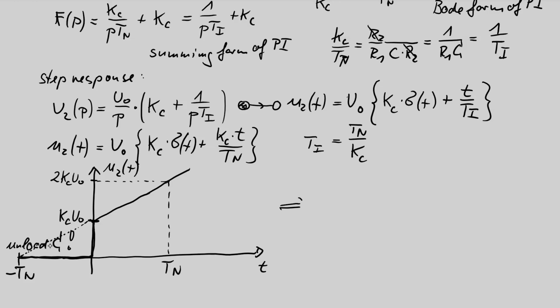This leads to the symbol of a PI, which is available in two versions. One version is this, with the parameters Kc and Tn at the top left. A PI is defined with these two parameters. Again, if we have an automatic reading system for symbols, this could be mixed up with my integrating symbol, because then the distance here defines the difference.